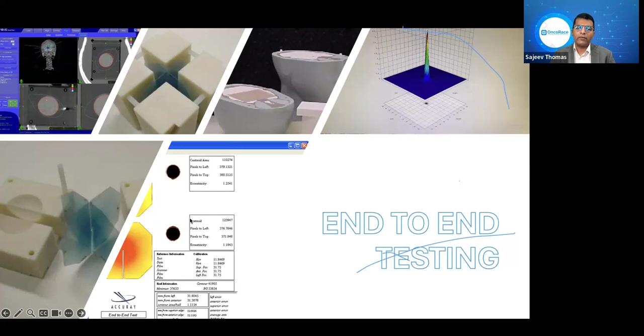But patient-specific quality assurance, on the other hand, only focuses on verifying the accuracy of the treatment plan and the dose delivery for each individual patient, identifying any discrepancies between the plan and delivered dose. So it is important to have end-to-end testing, which goes beyond the patient-specific quality assurance program. The reason is that end-to-end process control will help us identify the weakest link in the process.